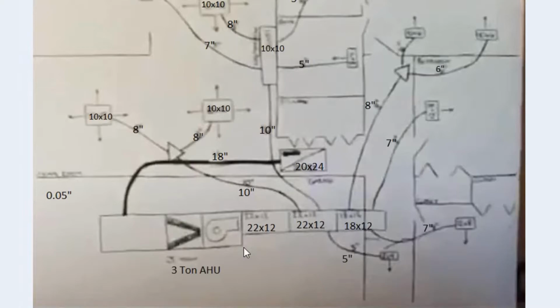The thing with air handlers is that they generally will come with a static pressure associated with them. Air handlers, unlike furnaces, take into account the actual evaporator coil and everything internal to that unit, whereas furnaces don't take into account evaporator coils. So air handlers will have a pressure rating of somewhere around 1/2 inch, and I'm going to work with this system based on that. I do not know if we have electric backup heat on here, so I have not taken that into consideration. I did not use any electric backup heat coils in calculating anything because his drawing here doesn't show any, so we're going to assume that there is no heat in this house.